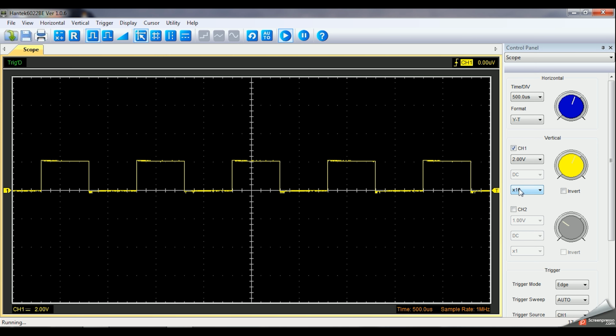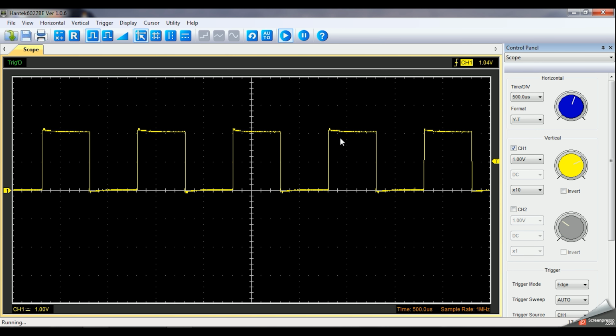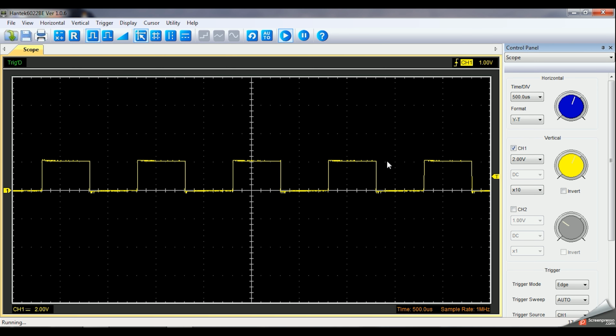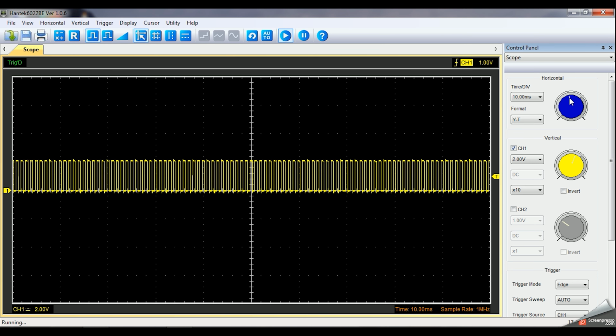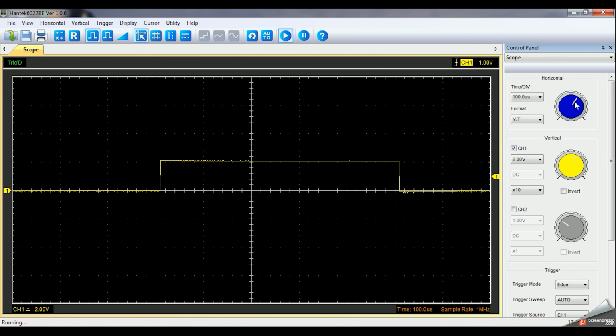Before you start with the tuning, the calibration of the probes, you will have to select the 10x on the channel 1 in the vertical section, and then you can just click on the auto button, so it will set all the values, and then you can set the peak voltage to 2 volts. When you want to zoom or change the time per division value, you can zoom in the waveform. You just have to use the blue knob in the horizontal section.